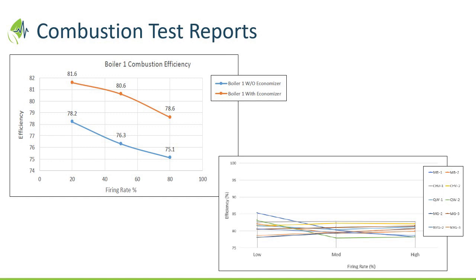Take a moment to fill that in, but there's a challenge left for these guys before we let them back to the seat. So combustion test reporting matters. On the left-hand side there is one of half a dozen charts that come, your excess air. There's a whole bunch of potential charts that come out of your test reports. Without being pejorative, the majority of hospitals never even look at those reports.